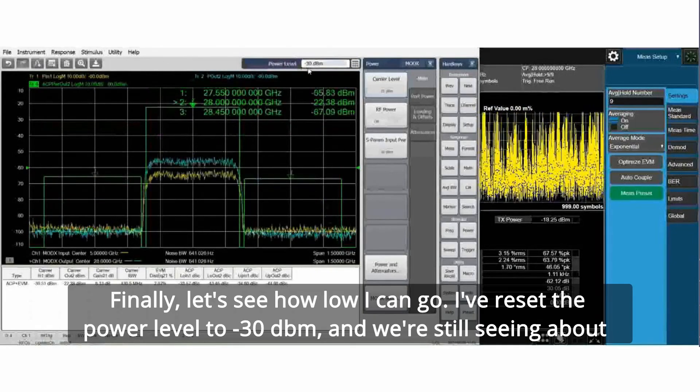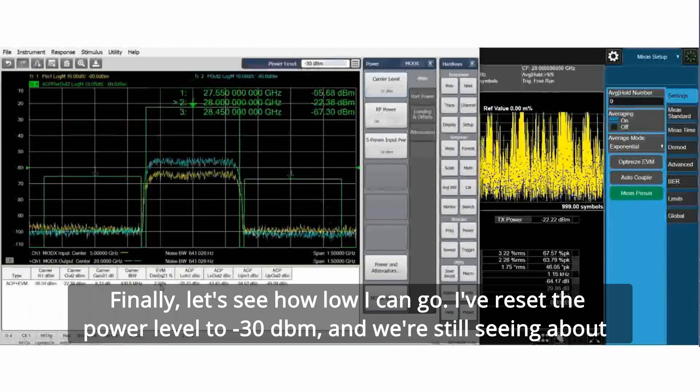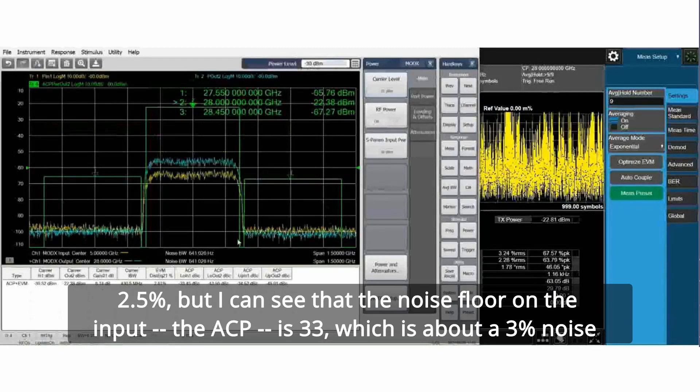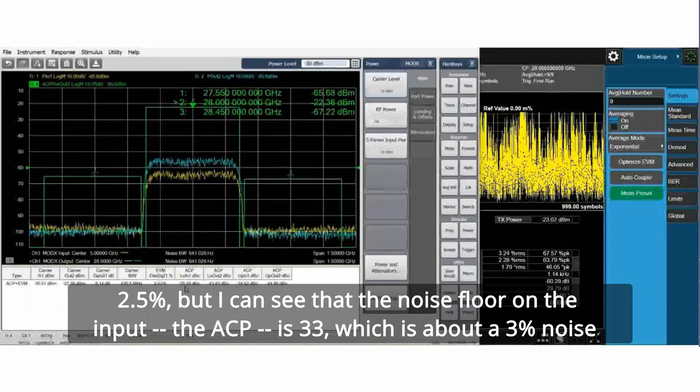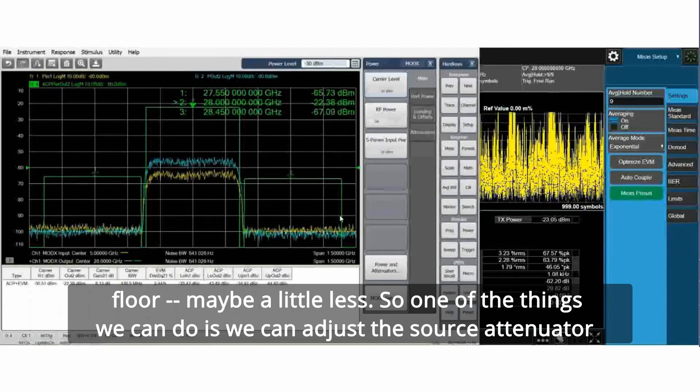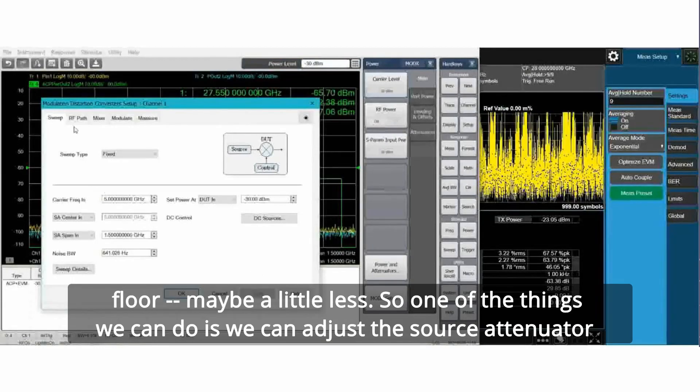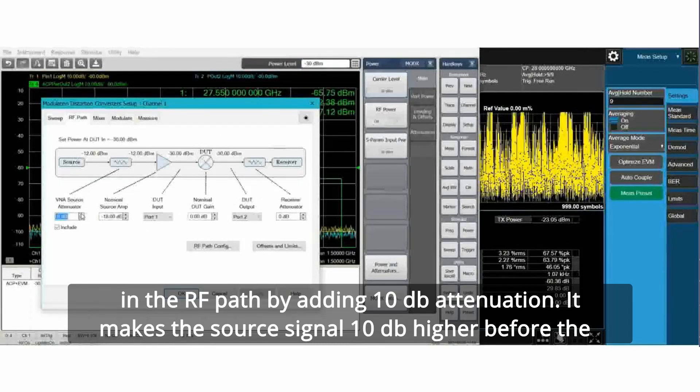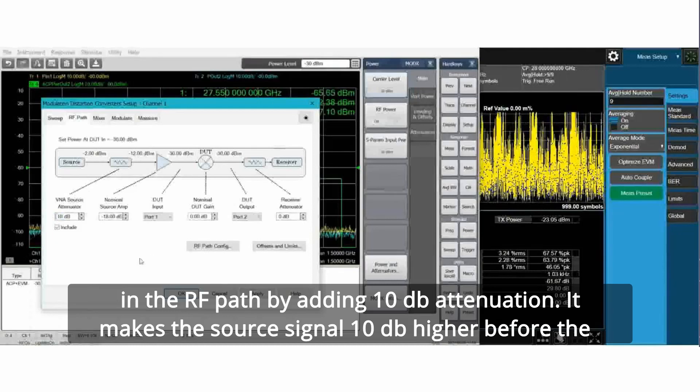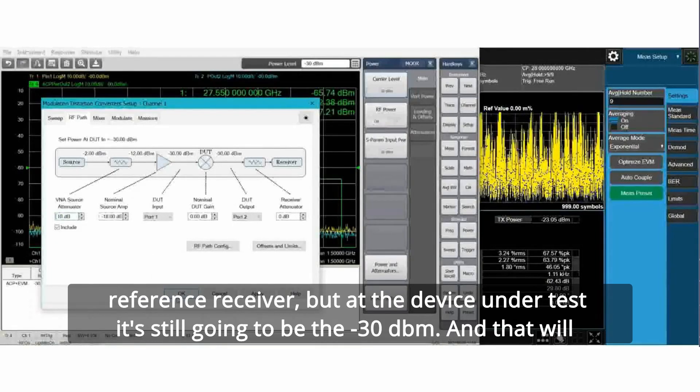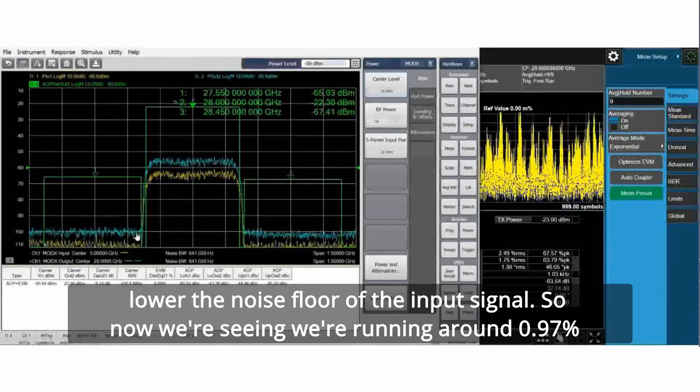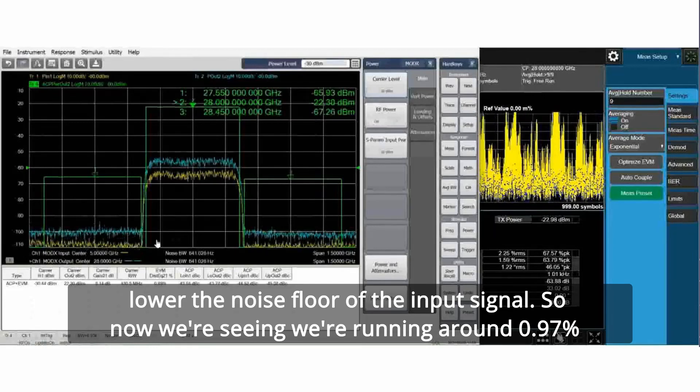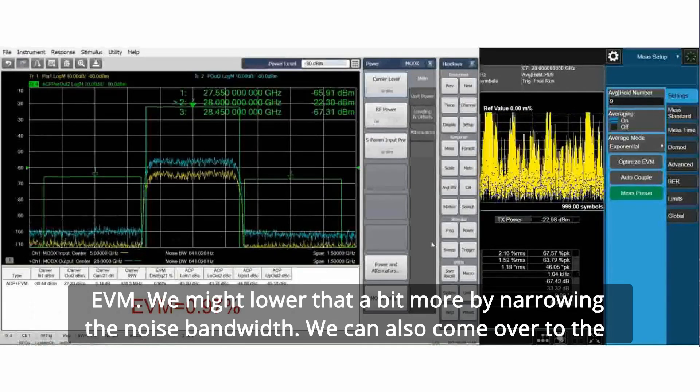Let's see how low I can go. I've reset the power level to minus 30 dBm. We're still seeing about 2.5 percent. But I can see that the noise floor on the input, the ACP is 33, which is about a three percent noise floor. So one of the things we can do is adjust the source attenuator in the RF path by adding 10 dB attenuation. It makes the source signal 10 dB higher before the reference receiver, but at the device under test, it's still going to be minus 30 dBm. That will lower the noise floor of the input signal. Now we're seeing we're running around 0.97 percent EVM.